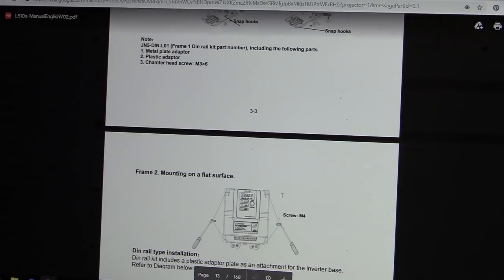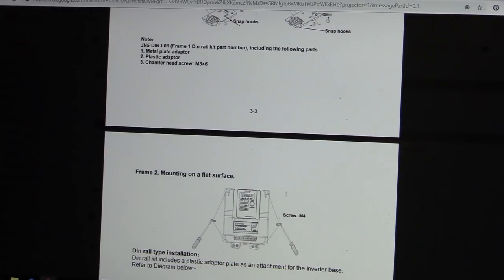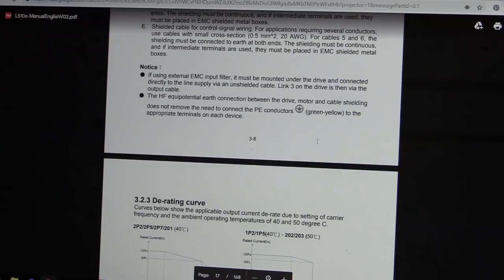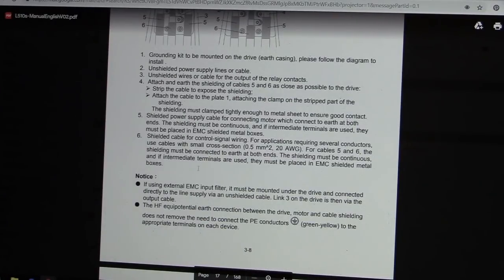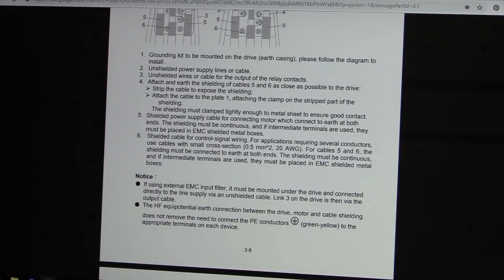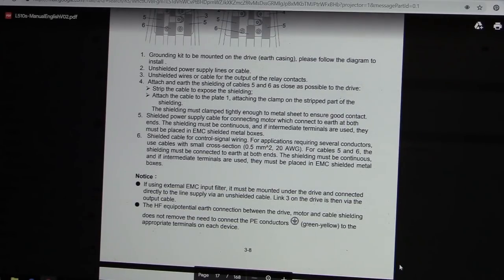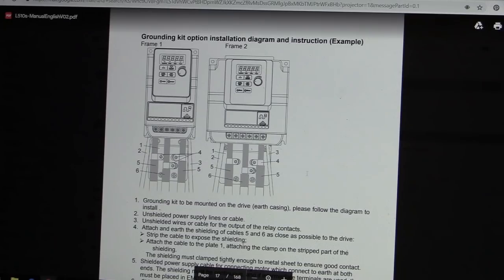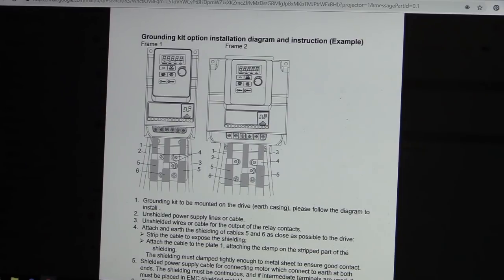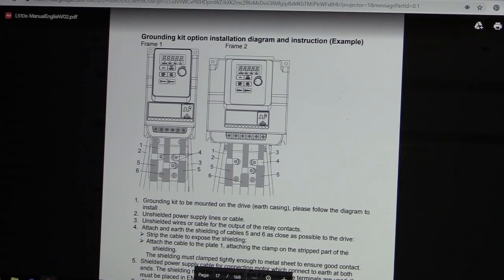This is the manual for the VFD I was considering buying but I didn't want to spend 150 quid on it just yet but maybe I will still. There is a lot of really interesting information and it is still worth a read. Here it says if using an external EMC input filter it must be mounted under the drive and connected directly to the line supply via an unshielded cable. You can see how they've shielded the cables, it's literally screwed directly onto the backing plate by the looks of it.